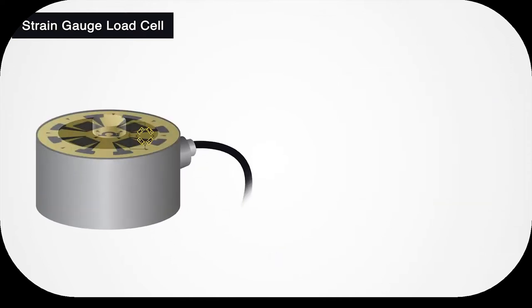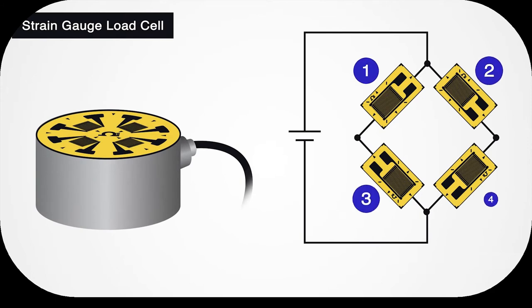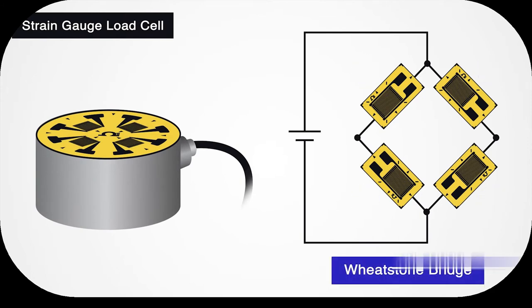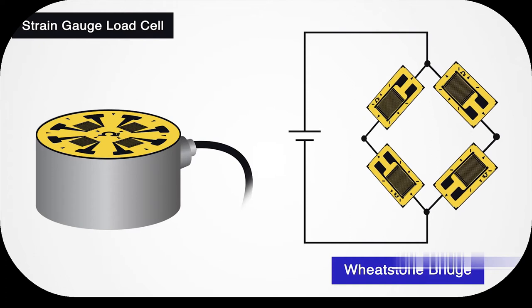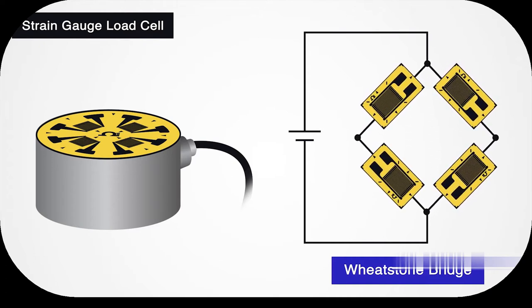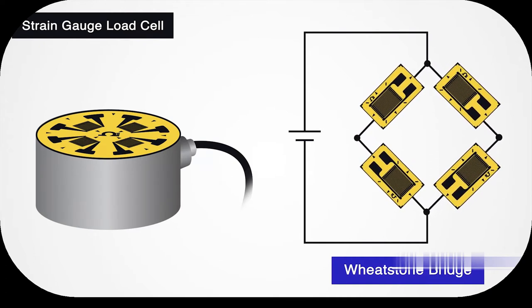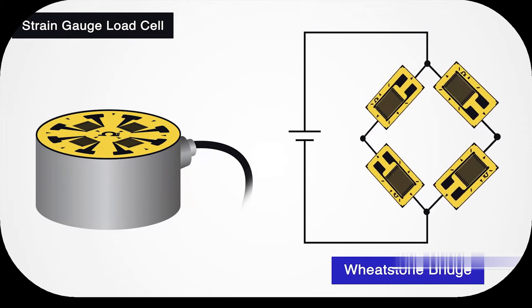A strain gauge load cell is made up of four strain gauges in a Wheatstone bridge configuration. A Wheatstone bridge is an electrical circuit that measures unknown electrical resistance by balancing two legs of a bridge circuit, one of which contains the unknown component. The Wheatstone bridge circuit provides incredibly accurate measurements. The strain gauges are bonded onto a beam which deforms when weight is applied.